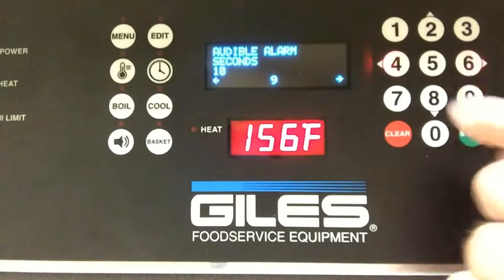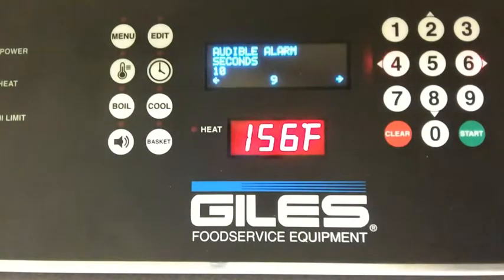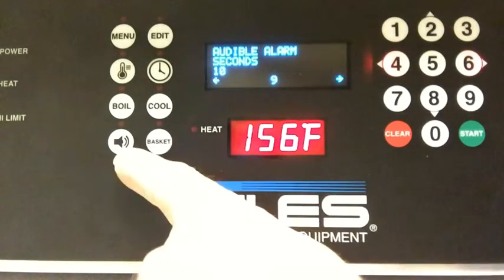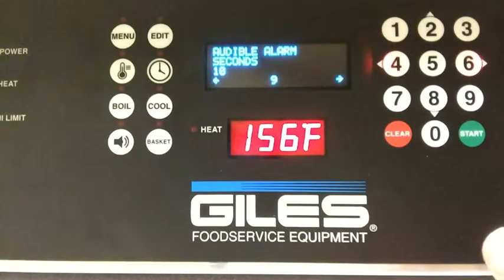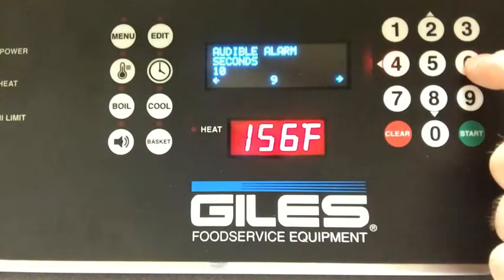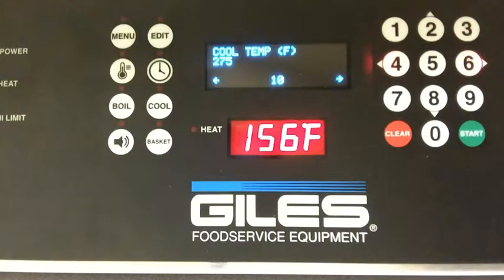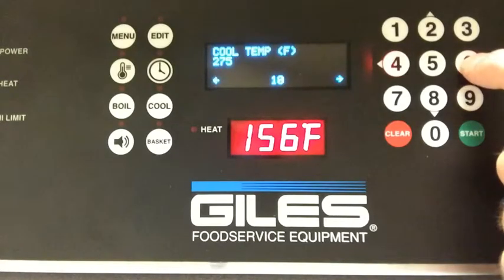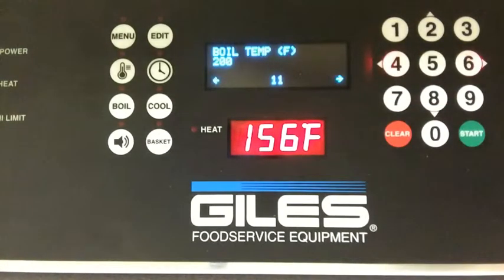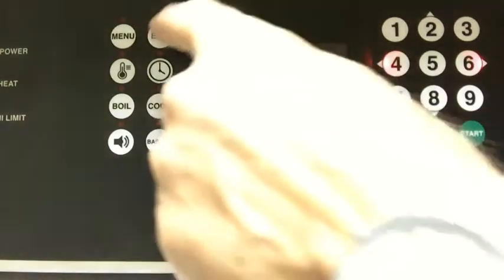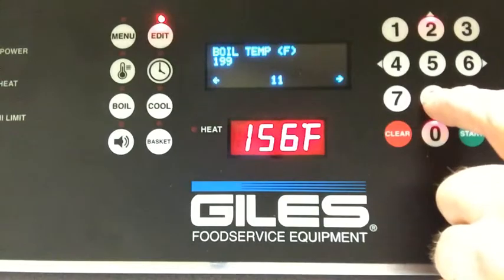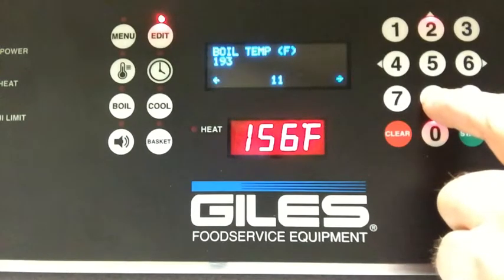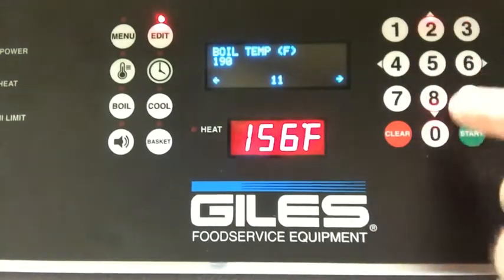Okay. The next one, Audible Alarm. That's how long the alarm will sound without anybody pressing the key. It'll silence itself after 10 seconds. The cool temperature. If you go into that cool mode, 275 degrees, that can be adjusted as well. The boil temperature, 200 degrees is standard. Again, at higher elevations, you may want to go ahead and bump this down to 190 or so. Okay.